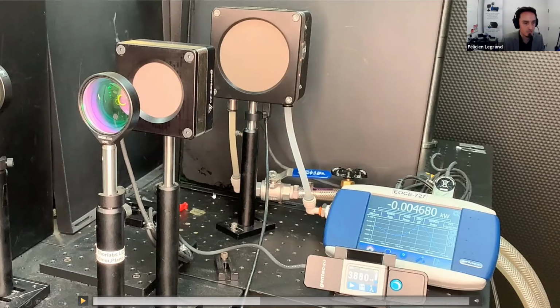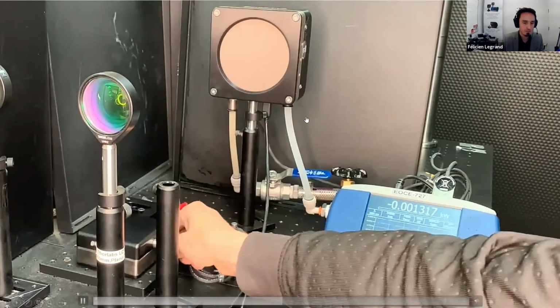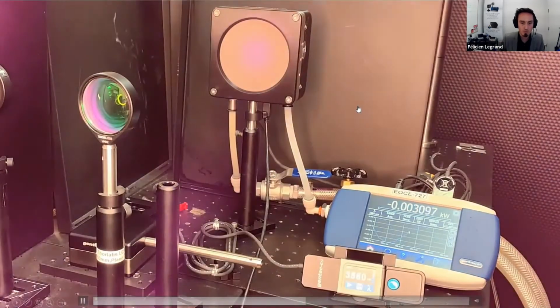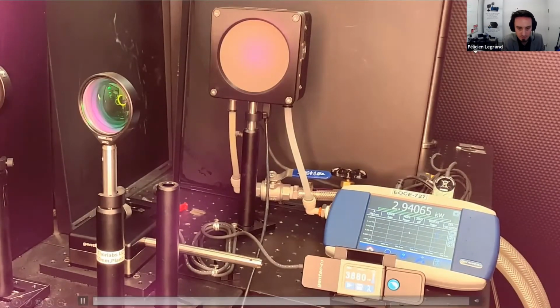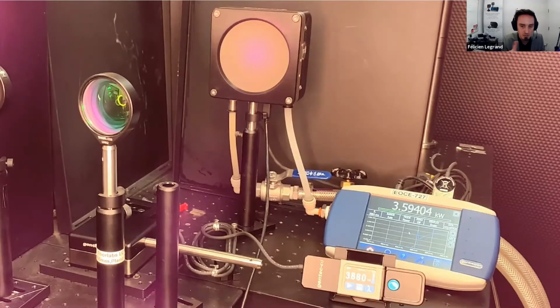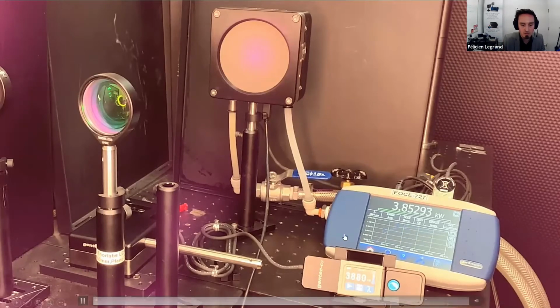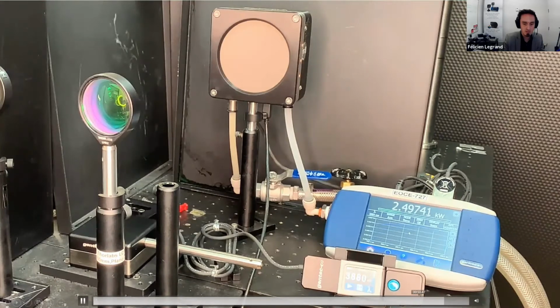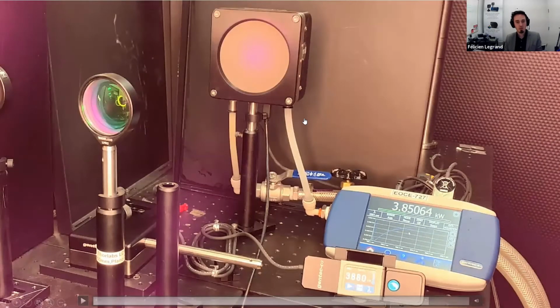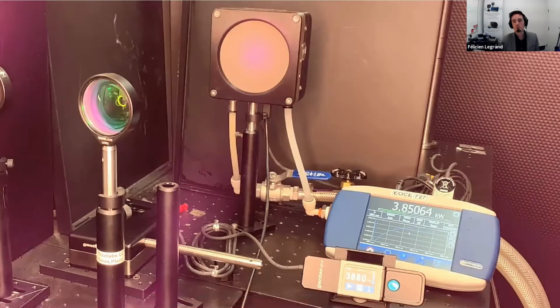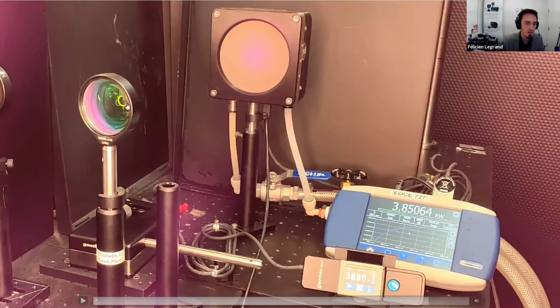But let's say you'd like to measure this kind of power for a longer period of time to see how your laser is behaving. Then we remove the first detector and let the other one take over, the one that's water cooled, so it can take whatever period of time we want to measure. I've accelerated this video 4 times just to get faster to the stabilized output. And we'll see the Maestro, the display here, go to 3.85 kilowatts, which is consistent with the other measurement, because you can apply a plus or minus 5% absolute accuracy, the calibration uncertainty, to this measurement. So the two measurements are consistent, and you can run this HP product, the one that is water cooled, once again for hours, for days.